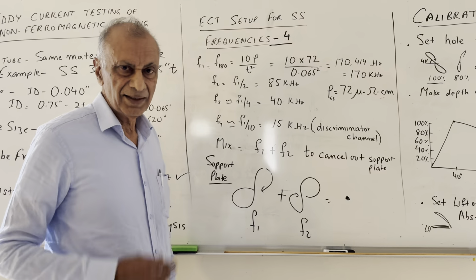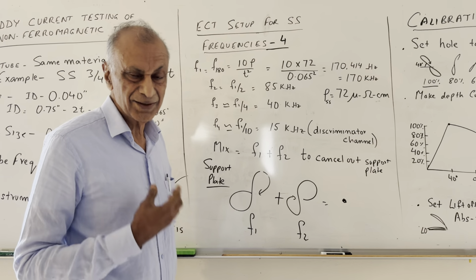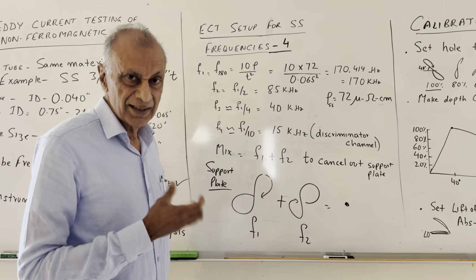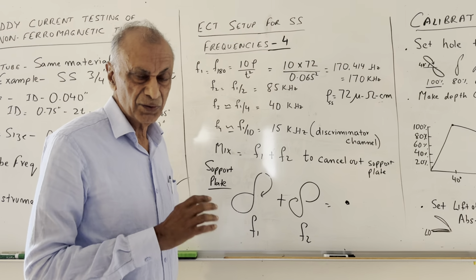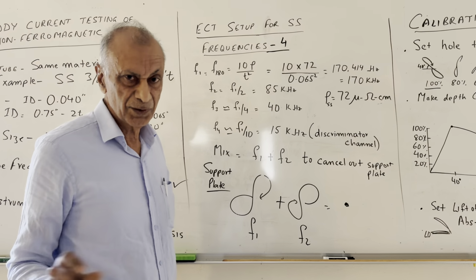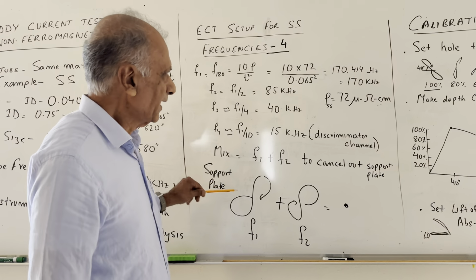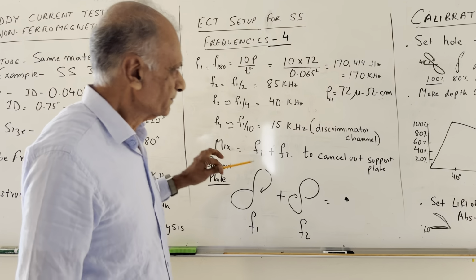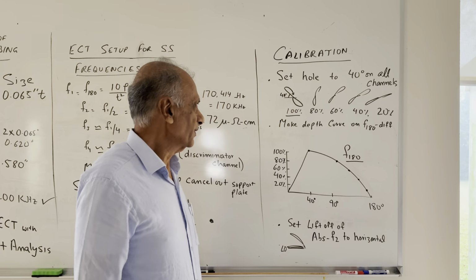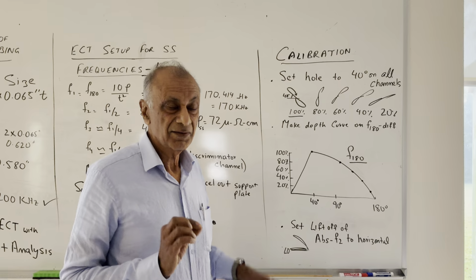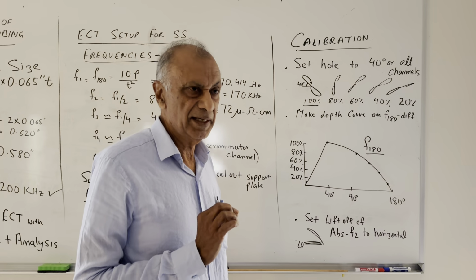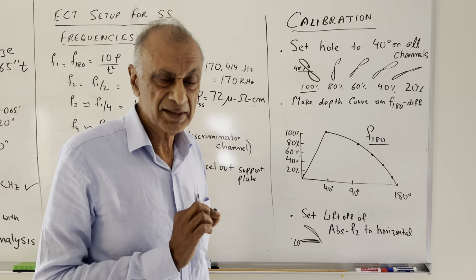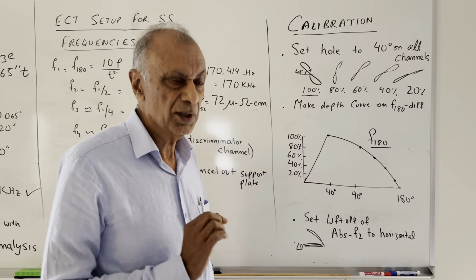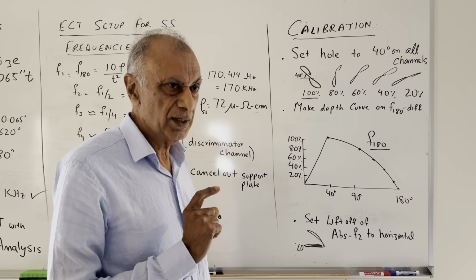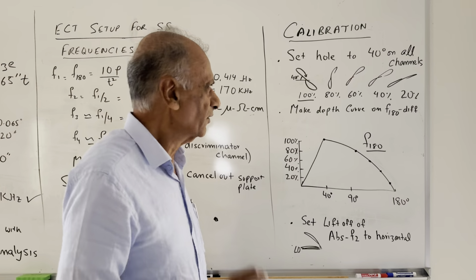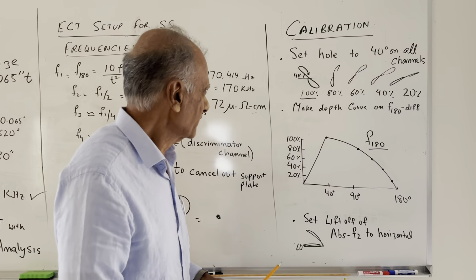So that's the reason to use the mix, is to get the support plate signal down to zero, so that you can find the discontinuities or the pits underneath the support plate also, because you have to inspect 100% of the tube length. Then we do the calibration. Okay, so now the calibration, which is the depth curve, should be created on the F1 frequency, not any other, not the F2, because the F1 will give you a phase spread of 180 degrees.